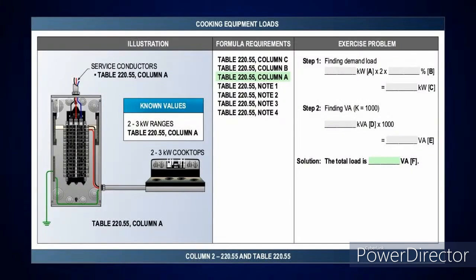Now this one here, I'm showing you two ranges here at 3 kW. Well, it's less than 3.5. I come down and I pick up 2. It tells me take it at 75% there. So I've got 2 of them, so it'd be 3 kW times 2, which is 6, and then you're taking it at 75%. That's going to be your demand load.